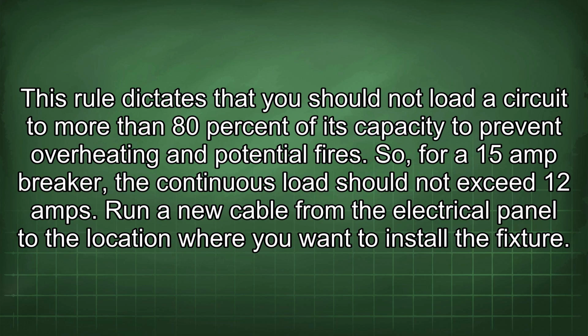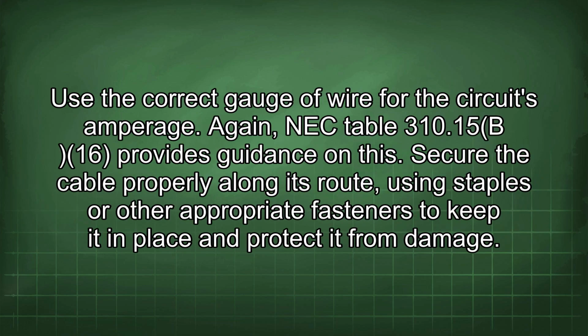Run a new cable from the electrical panel to the location where you want to install the fixture. Use the correct gauge of wire for the circuit's amperage. Again, NEC Table 310.15(B)(16) provides guidance on this.